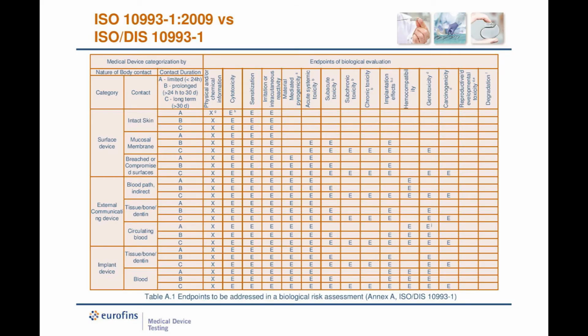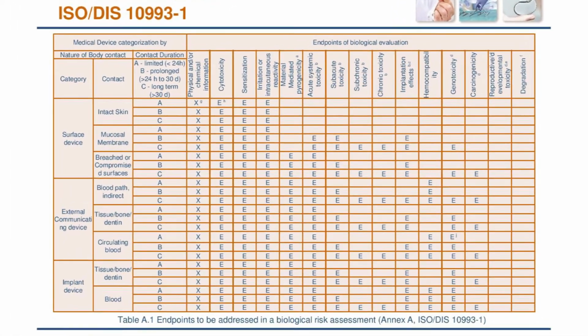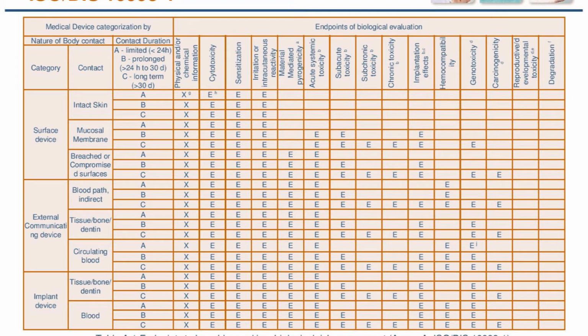Also, at the first glance, you can see that it's really different from the previous one because there were included a lot of columns and a lot of information about the endpoints of the biological evaluation. And in the next slide, we will focus on these differences, but let's start to think about the title of the table. In the past, this table was called Evaluation Test for Consideration, so it was really focused on tests. Now this table is called Endpoints to be addressed in a biological risk assessment. So as a first glance, we can understand how the biological risk assessment is now really, really important and plays an important role in the biological evaluation and demonstration of the safety of our device.